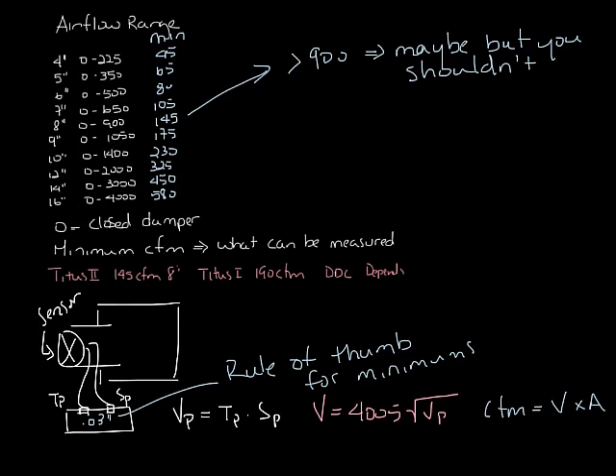Ideally, you'll want to keep the velocity through the inlet around 2,000 or 2,200 feet per minute. So let's look at that 8-inch box again.